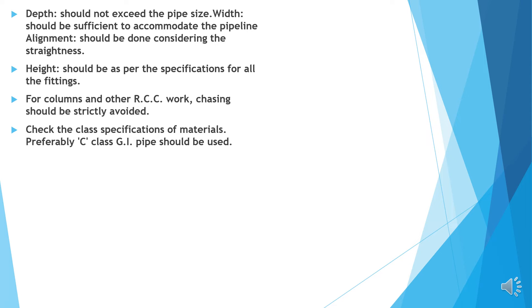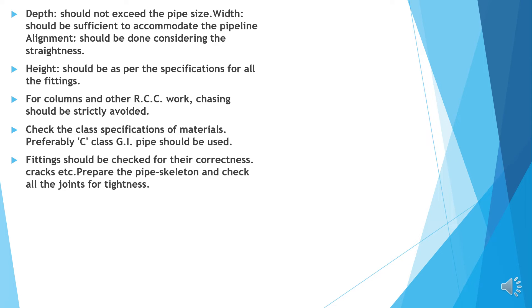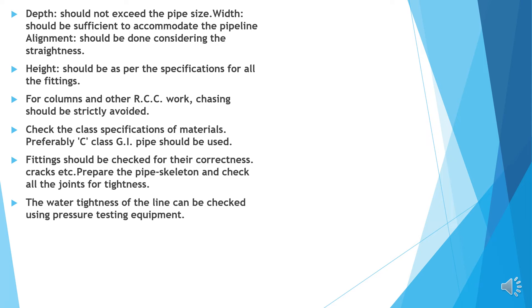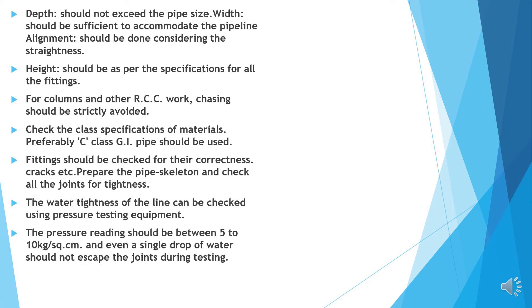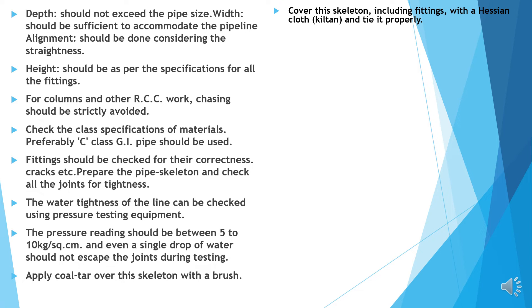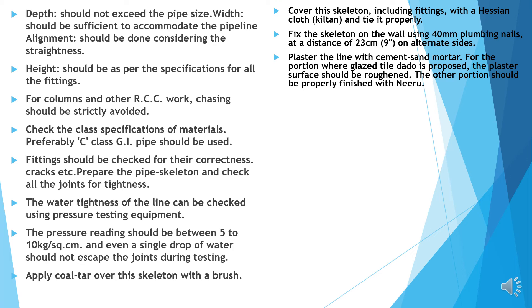Check the class and specification of the material — preferably C class GI pipes should be used. Fittings should be checked for correctness, cracks, etc. Prepare the pipe skeleton and check all joints for tightness. The water tightness of the line can be checked using pressure testing equipment. The pressure reading should be between 5 to 10 kg per cm². Not even a single drop of water should escape the joints during testing. Apply coal tar over the skeleton with a brush. Cover the skeleton including fittings with hessian cloth and tie it properly. Fix the skeleton on the wall using 40 mm plumbing nails at a distance of 9 inches on alternative sides. Plaster the line with cement and sand mortar, roughening the surface where glazed tile dado is proposed. Curing should be done for at least 7 days.